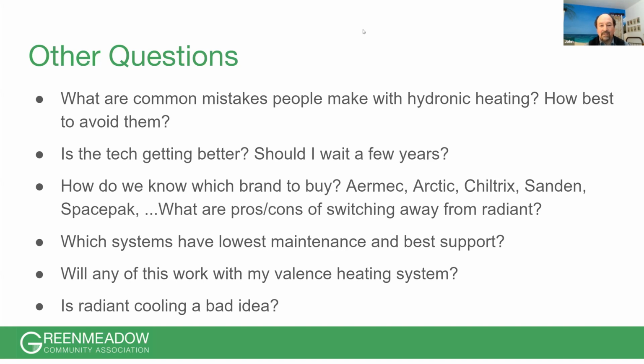Then there's the heat pump outside. We've sold almost 200 units of the Chiltrix in the last 2.5 years. We've had like 3 or 4 boards go out, and maybe 4 flow switches. And we figured out what was wrong with the flow switches, and that was the original batch didn't have silicone in a certain spot, and if the unit went to cooling, condensation was collecting on that electrical part of the switch. And so now we have that spot filled in with silicone and don't have that issue.